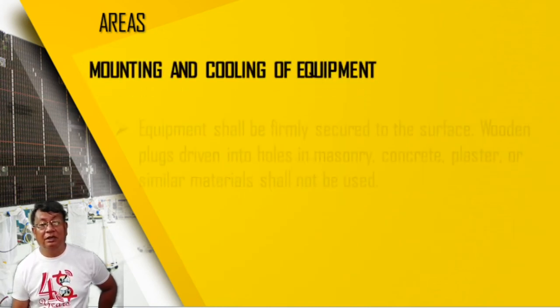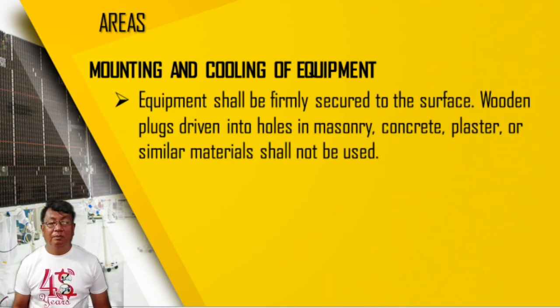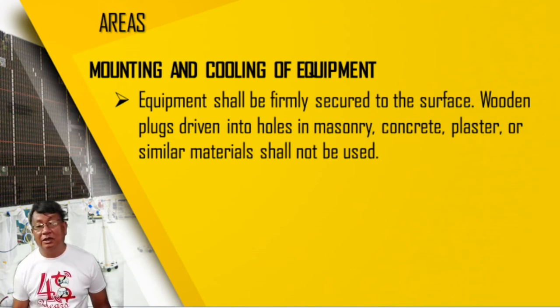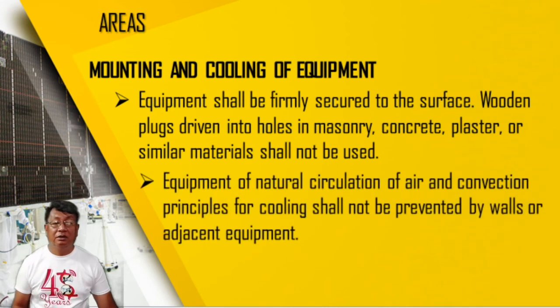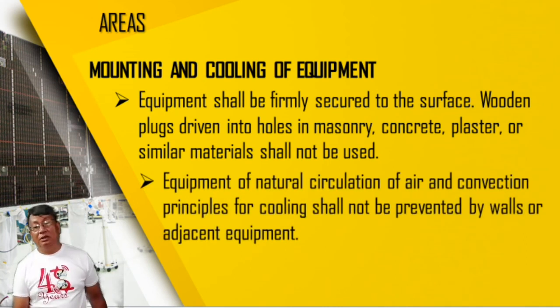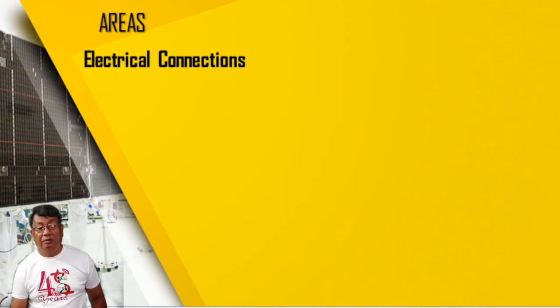Okay, so mounting and cooling of equipment. Equipment shall be firmly secured to the surface. Wooden plugs driven into holes in masonry, concrete, plaster or similar materials shall not be used. So they are not allowed. Equipment relying on natural circulation of air and convection principles for cooling shall not be prevented from doing so by walls or adjacent equipment. So electrical connections.